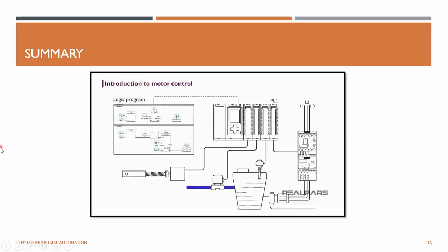As automation engineers, we write logic programs for PLC and DCS systems that monitor process variables, open and close valves, set control loop modes, and start and stop motors for pumps, compressors, and conveyor systems. Most digital outputs on control systems operate on 24-volt DC or 120-volt AC. So how do I start and stop three-phase 480-volt AC industrial motors? The simple answer is by using a motor controller.